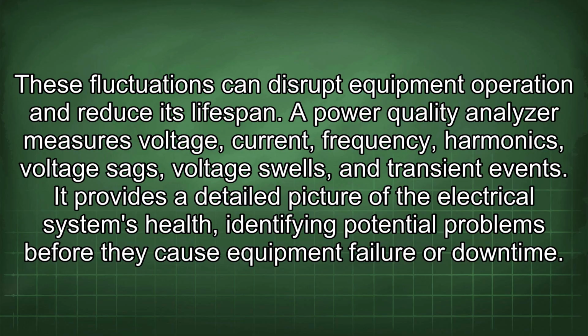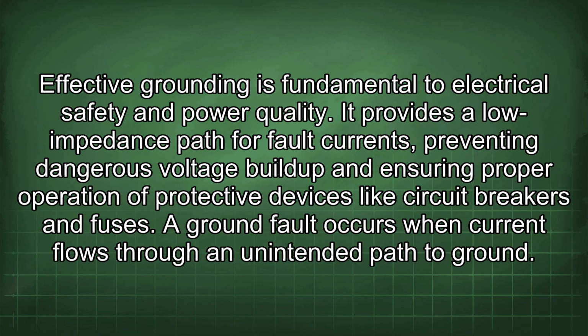A power quality analyzer measures voltage, current, frequency, harmonics, voltage sags, voltage swells, and transient events. It provides a detailed picture of the electrical system's health, identifying potential problems before they cause equipment failure or downtime. Effective grounding is fundamental to electrical safety and power quality. It provides a low impedance path for fault currents, preventing dangerous voltage buildup and ensuring proper operation of protective devices like circuit breakers and fuses.